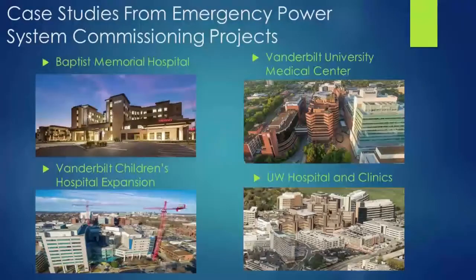test. On your bottom right is UW Hospital and Clinics, and that's in Madison, Wisconsin. It's an existing facility, roughly 1.3 million square feet, 616 bed, level 1 trauma center. It has 3 paralleled 2,500 kW medium voltage gen sets. It is a split bus configuration with 13 ATSs connected in phase 1 and approximately 40 ATSs as part of phase 2 testing.